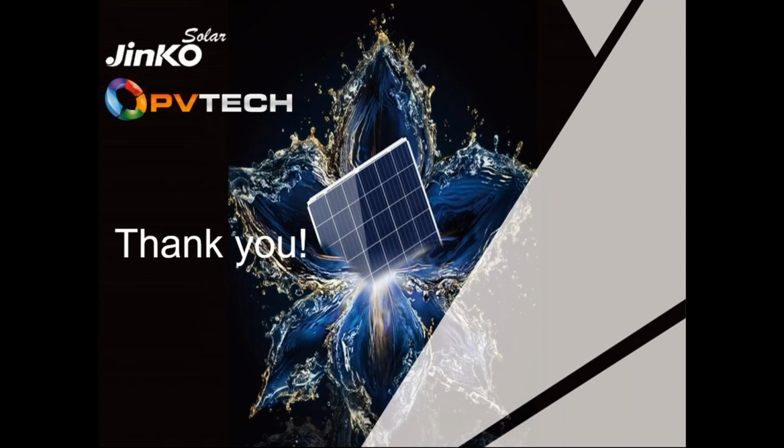So far, all our panels can withstand all the standards. Also, the total standard conditions from the IEC will be respected. The only point of PID is that material matters. That's why we are trying to deliver the best backsheet, the best frame, the best glass in order to avoid the PID effect. In the market, of course, the best panel that can be PID-free is the glass-glass module, which is actually really PID-free. But for standard models with frame, glass, and backsheet, we have PID resistance, and we try to do our best in order to avoid this phenomenon, choosing the best material around the panel.